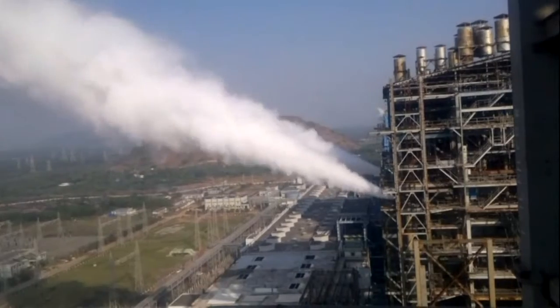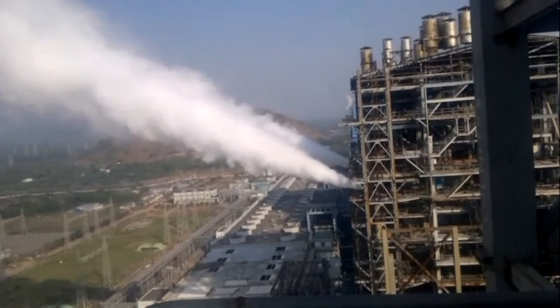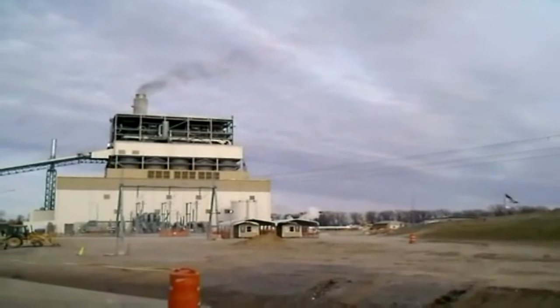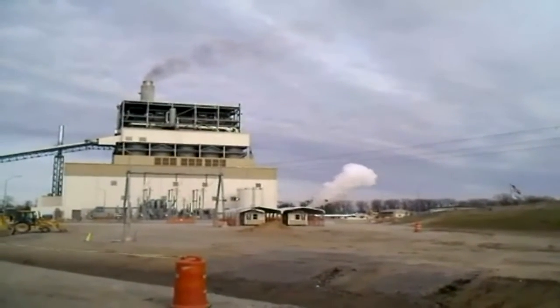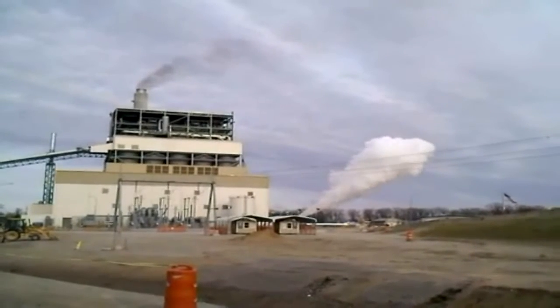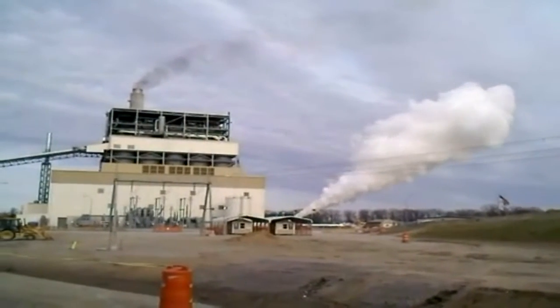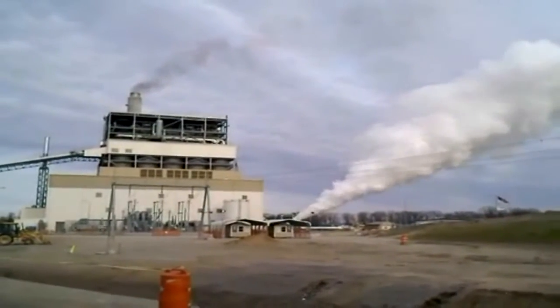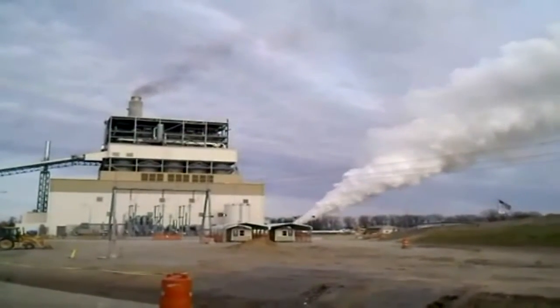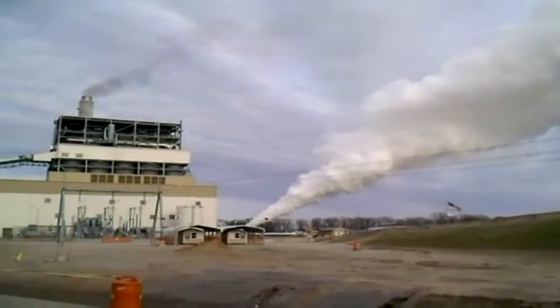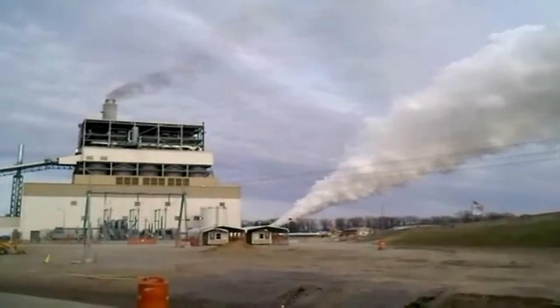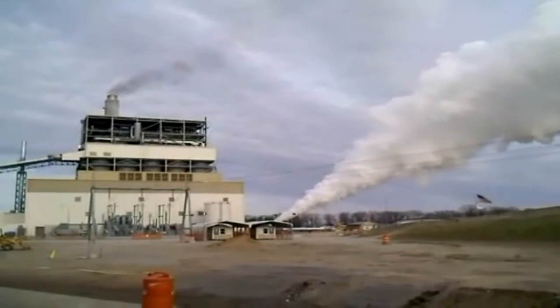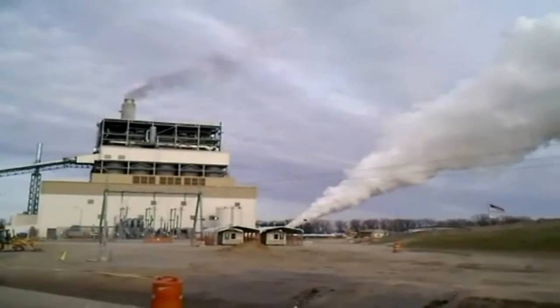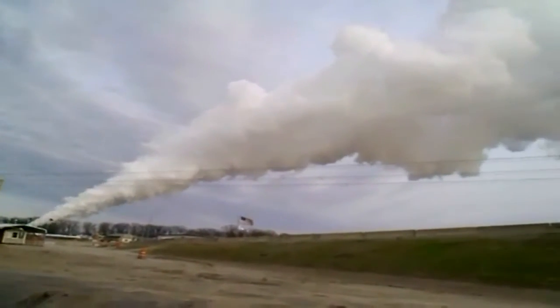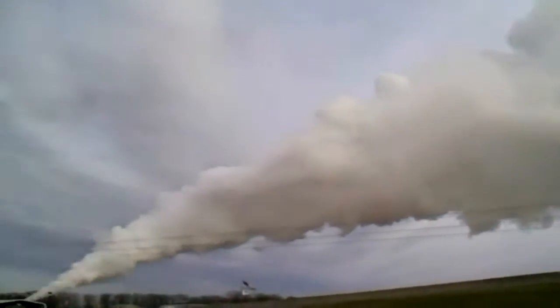There is considerable disruption with steam blowing, and it will have a significant impact on other site activities. Seek to mitigate this by having steam blows at off-peak times, such as lunch breaks or shift changes. There is a risk of damage to pipework and internal items. Take all proper safety precautions, such as erecting barriers and restricting access. Consider using baffles or silencers, especially to minimize impact on neighboring communities. Lag piping for personnel protection. Ensure all personnel in the area use hearing protection. Install structural anchoring at the exhaust, and mitigate risk of damage with relief of steam and debris at the exhaust.